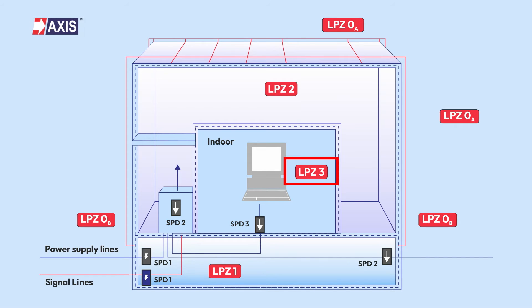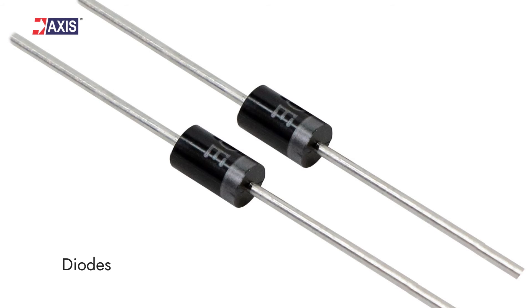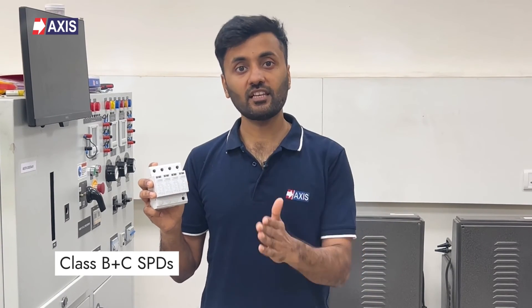Type 3 SPDs, also known as class D SPDs, are recommended in LPZ3 areas. These SPDs have a low energy handling capacity and are installed at the endpoints of the electrical system, such as your socket, so they can respond quickly during a surge. Materials like diodes are used in their construction, allowing them to manage surges safely. Type 1 plus 2 SPDs, also known as class B plus C SPDs, are installed in panels where cables enter from outside a building. Made using a combination of MOVs and spark gaps, they are more economical compared to Type 1 SPDs.